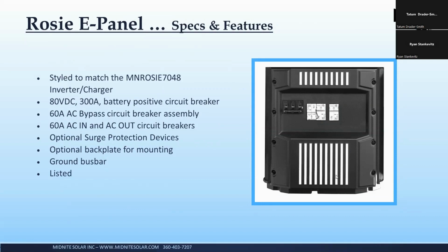You'll notice that we've gone to what we call a Z-wire for the bypass. So anybody in the room that's used our E-panels in the past, especially the one for the Schneider or the SMA, knows that when you take the dead front off to work on it, you take the bypass slider off, and now the breakers are no longer interlocked. And that always sort of bothered me a little bit. So the Rosie, we're transitioning to the Z-wire and everything, but on the Rosie E-panel, that makes it really nice because with the dead front off, the breakers are still interlocked.